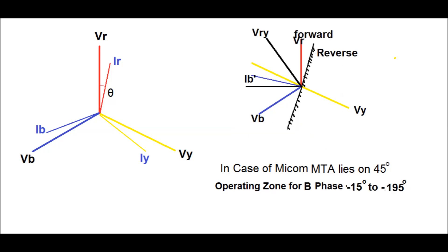Similarly, for a fault at blue phase, the reference voltage taken is VRY, that is the voltage between red phase and yellow phase. Since the maximum torque angle lies at 45 degrees, IB' leads by 45 degrees from VRY. Therefore, the operating zone for B phase lies between minus 15 degrees to minus 195 degrees. This zone is treated as a forward zone, that is the directional forward zone for relay fault at B phase. Beyond this zone, the relay will act in the reverse zone or blind zone — that is, beyond this zone, the relay will not sense any fault.